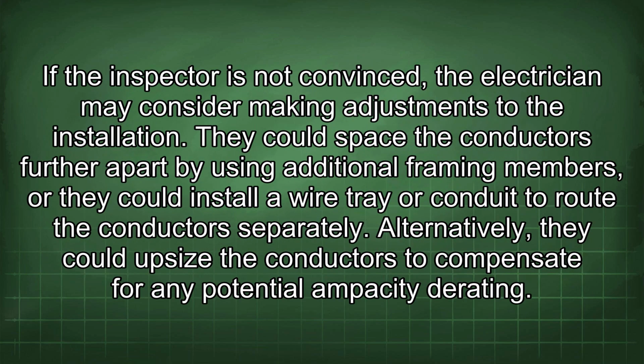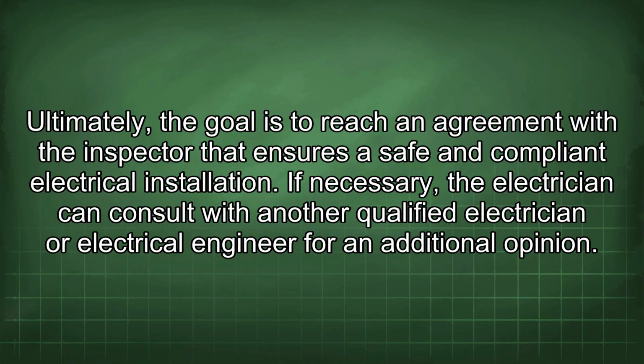If the inspector is not convinced, the electrician may consider making adjustments to the installation. They could space the conductors further apart by using additional framing members, or they could install a wire tray or conduit to route the conductors separately. Alternatively, they could upsize the conductors to compensate for any potential ampacity derating. Ultimately, the goal is to reach an agreement with the inspector that ensures a safe and compliant electrical installation. If necessary, the electrician can consult with another qualified electrician or electrical engineer for an additional opinion.